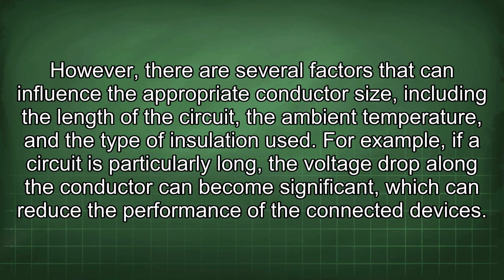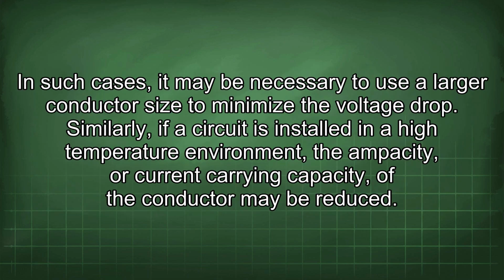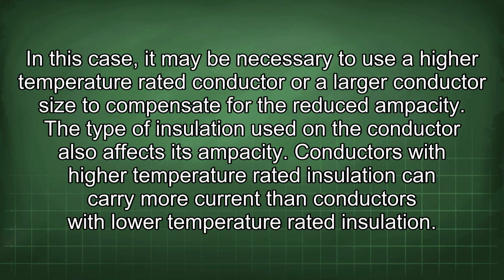For example, if a circuit is particularly long, the voltage drop along the conductor can become significant, which can reduce the performance of the connected devices. In such cases, it may be necessary to use a larger conductor size to minimize the voltage drop. Similarly, if a circuit is installed in a high-temperature environment, the ampacity, or current carrying capacity, of the conductor may be reduced. In this case, it may be necessary to use a higher temperature rated conductor or a larger conductor size to compensate for the reduced ampacity.